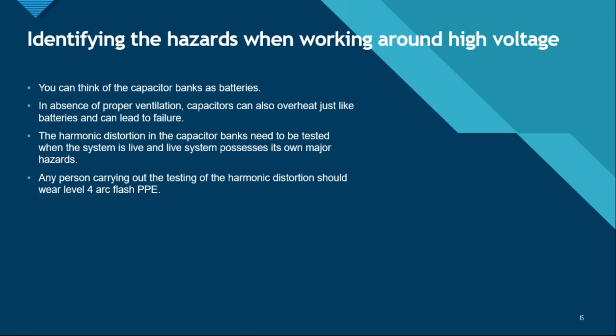All right. In the absence of proper ventilation around capacitor banks, capacitors can also overheat, just like batteries do, and can lead to failure of the capacitor banks as well. The harmonic distortion in the capacitor banks needs to be tested when the system is live, and a live system possesses its own major hazards, right?